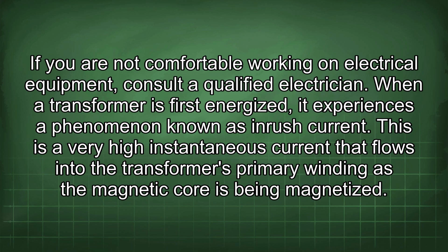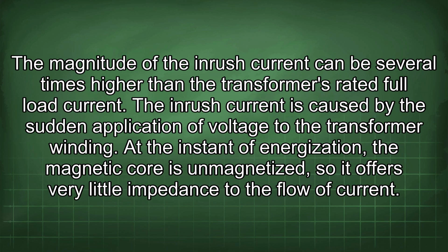When a transformer is first energized, it experiences a phenomenon known as inrush current. This is a very high instantaneous current that flows into the transformer's primary winding as the magnetic core is being magnetized. The magnitude of the inrush current can be several times higher than the transformer's rated full load current. The inrush current is caused by the sudden application of voltage to the transformer winding.